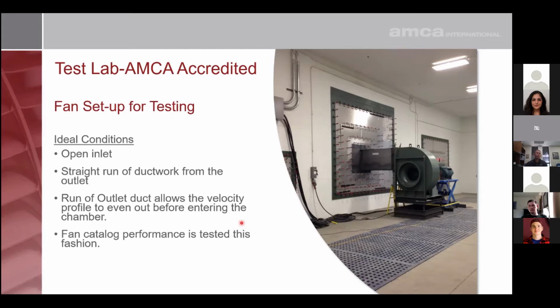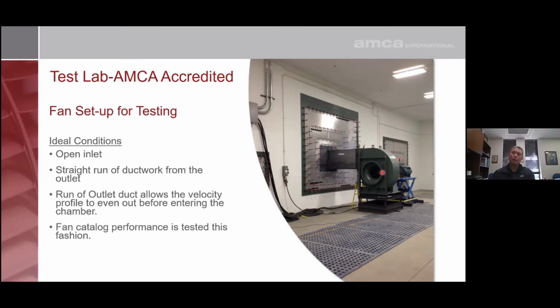So looking at this fan in the lab, you notice a couple things. One is the fan has an open inlet. Hopefully you can see my red pointer at the fan inlet, and that open inlet has a bell mouth to it. The purpose of the bell mouth is to allow uniform loading of the fan wheel, and secondly, to eliminate inlet velocity pressures. So basically it's a free open inlet and we don't have any obstructions at that point. On the discharge of the fan, straight run of ductwork. And that straight run of ductwork allows for the velocity profile of the air as it discharges the fan to even out. And we'll talk about that a little bit later.